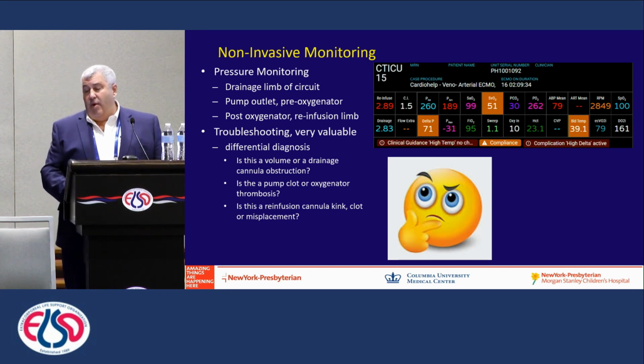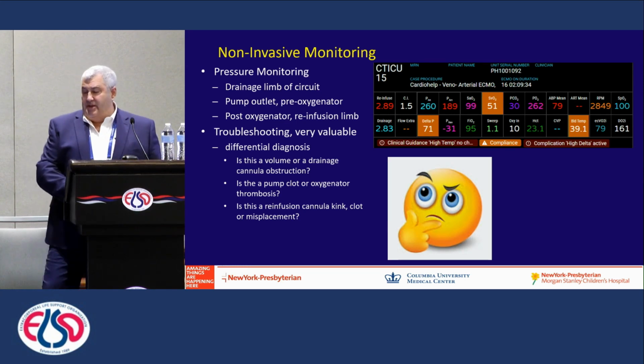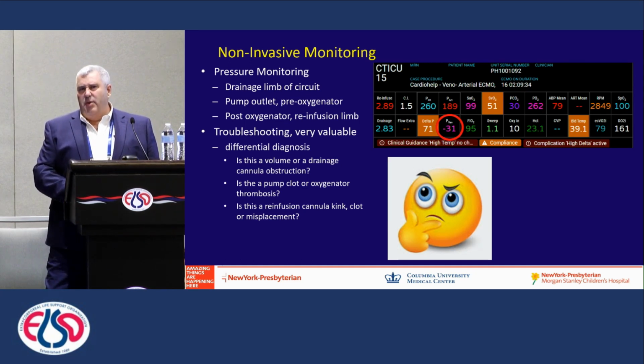So if we take our gauge bar, and this is our common gauge bar that you see up here on the top right, as we're trying to troubleshoot, we look and we go, well, the venous pressure is minus 31, so at 2.9 liters of flow, minus 31 is pretty reasonable, so we don't think this is a venous cannula issue. If we look at the reinfusion pressure between the pump head and the oxygenator, 260 millimeters of mercury for our particular circuit at a flow of a little under 3 liters, that's a high number, much higher than we would anticipate. So now we know it's definitely some issue that's distal to the pump head.